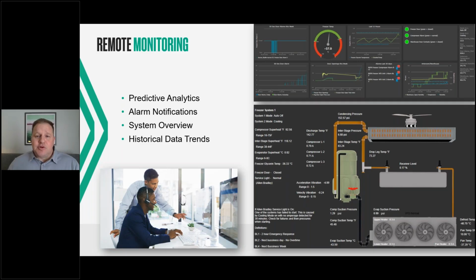Instead of the typical way a lot of these plants run, where somebody sees the system went down, sees a temperature spike, and calls, our goal is to know that they've lost something. We've seen superheats out of range, we see high discharge, and we send a guy before that ever has a chance to impact them or the product. The goal is it runs and they don't even know that it's there. It just keeps things at temperature.